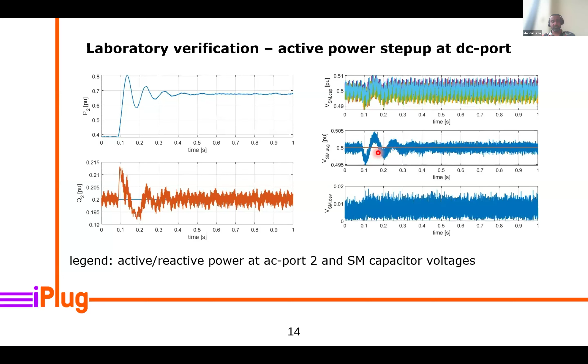And of course, we have to test also a number of unbalanced operation or abnormal tests like faults and unbalanced operations. With a conventional operation, if we apply one phase fault, a little bit of a dip, we could see that there will be unbalanced current exchange, which affects the active and reactive power exchange, and the circulating currents or the currents in the arms of the modular multi-level converter will be a bit unbalanced. By applying, of course, ways to mitigate the negative sequence components in here or the imbalances in the arm currents, it's possible to have a full balanced exchange on the AC side or the DC side.